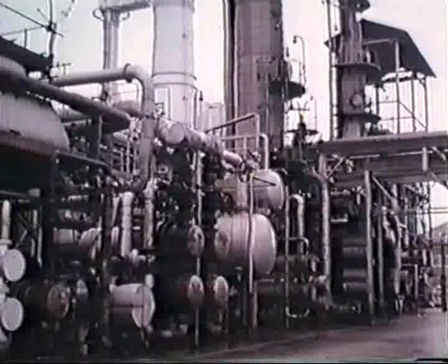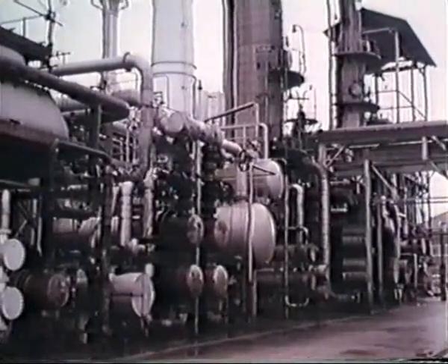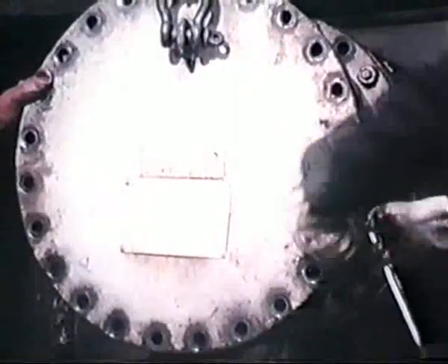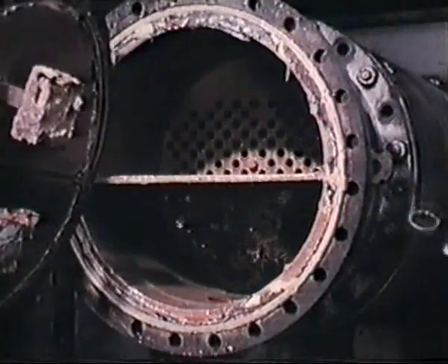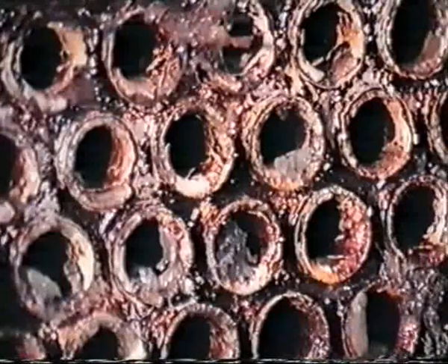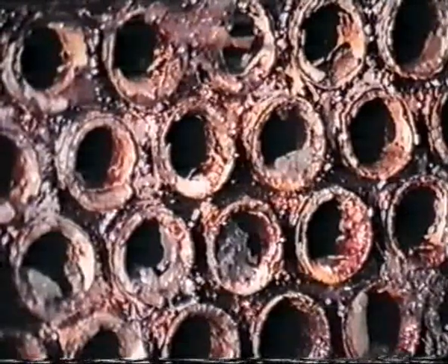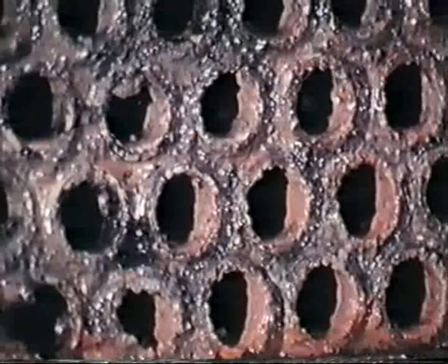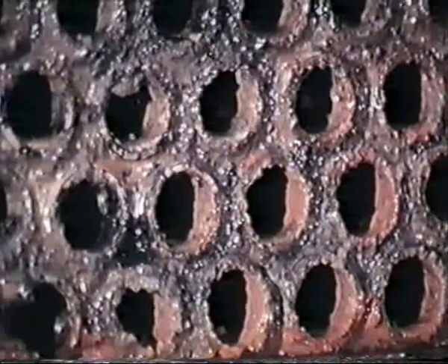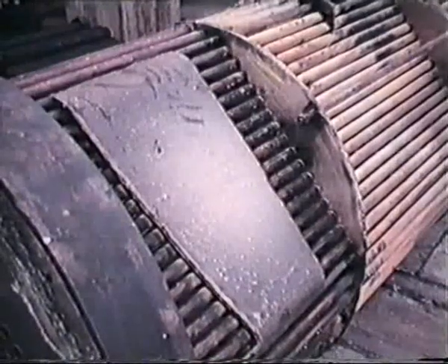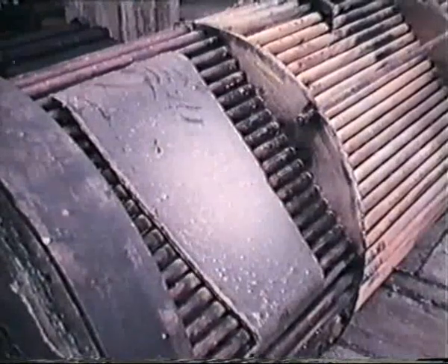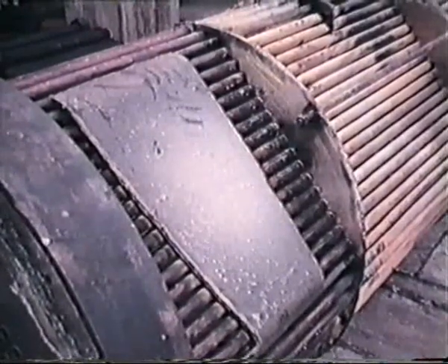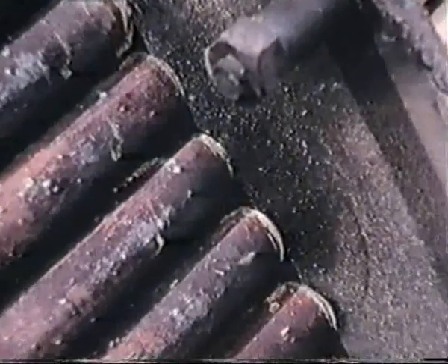In industry, erosion corrosion causes many problems in cooling water systems, and most can be overcome by design. With many heat exchangers, where seawater is used as a coolant, in spite of filters, inlet pipes are seen at maintenance to be partially blocked with debris. This can affect flow and give turbulence, which in turn can increase erosion corrosion. This can also occur on the outside of tubes. An incorrectly designed baffle to deflect hot products led to these streaming through the narrow gap between tube and support.